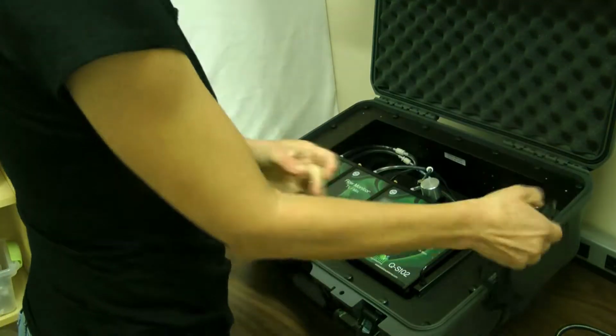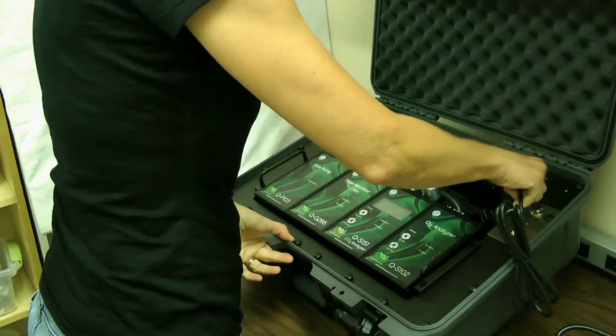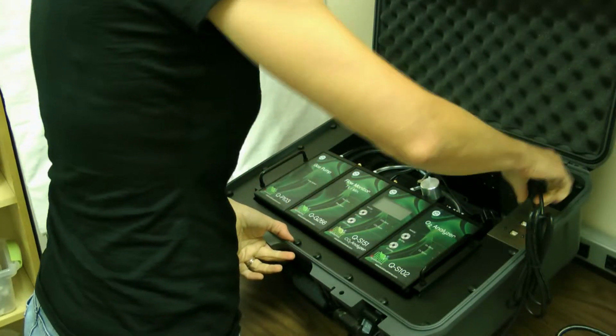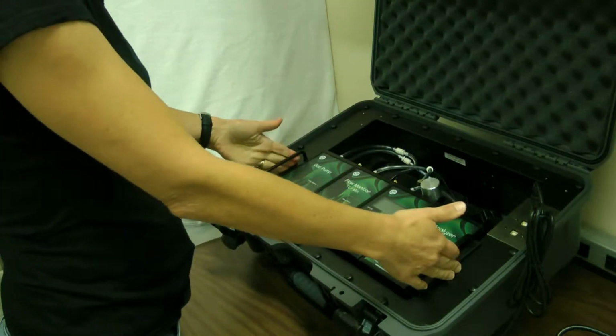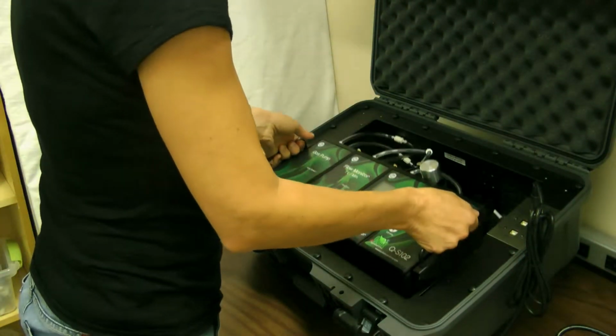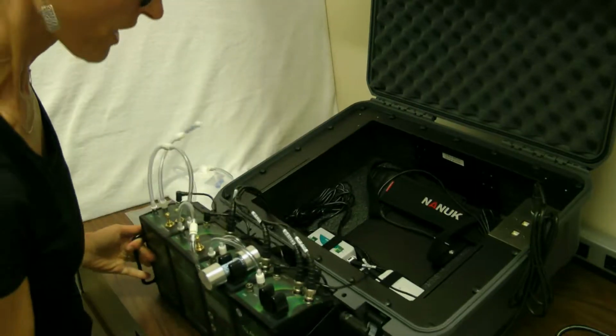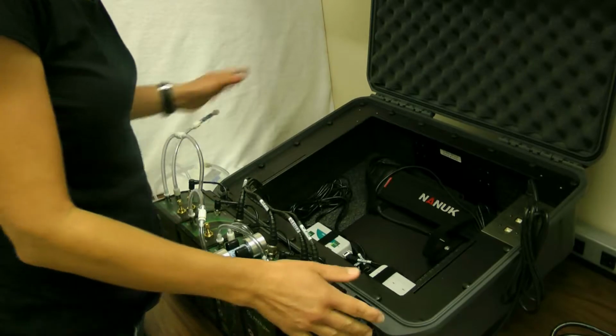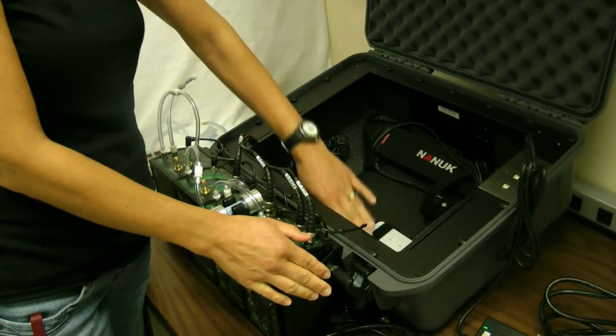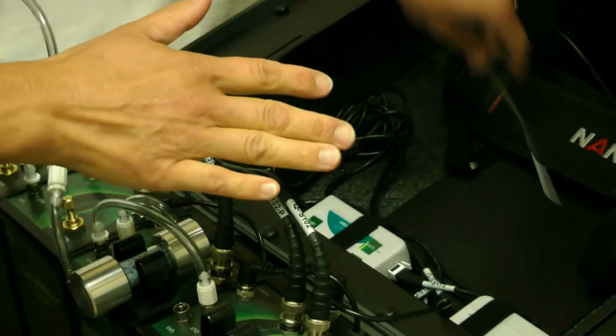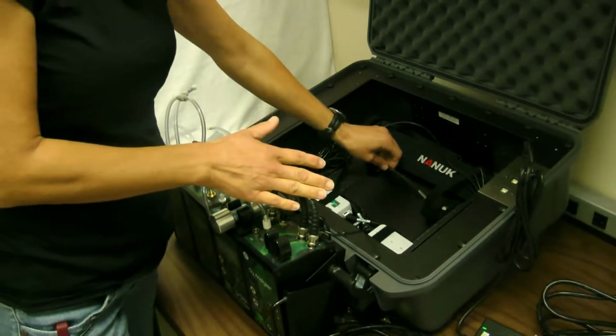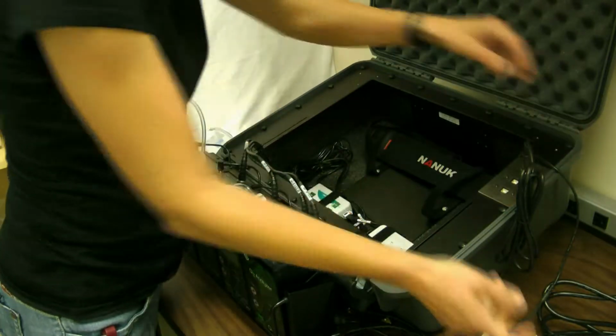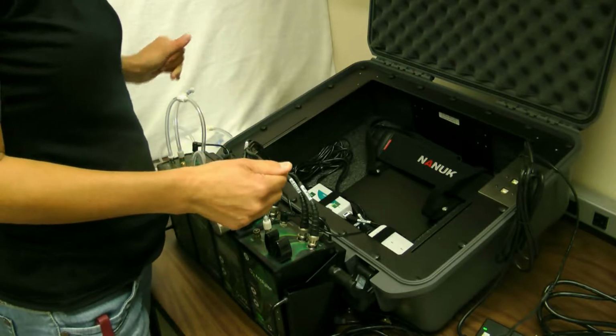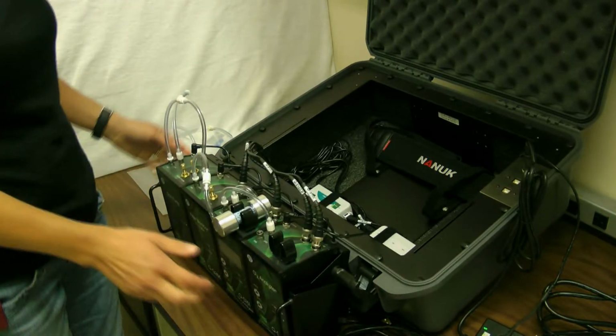You plug in your power supply. The power input goes on the side of the Q-Box, right there. This is the tray with all of the analyzers. Initially, remove the tray out so you can check the plumbing and make sure everything is in order. There's two data interfaces at the bottom of the Q-Box to which the sensors are attached, and there's a temperature probe inside the Q-Box as well, which can be taken out for measuring temperature either of your sample or the environment. So initially you're checking your plumbing.